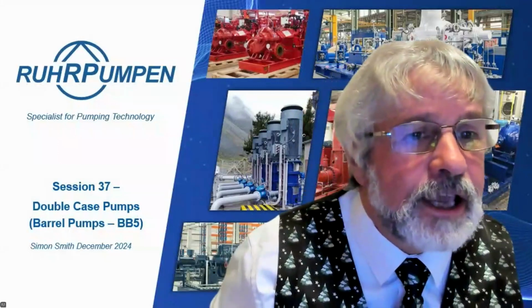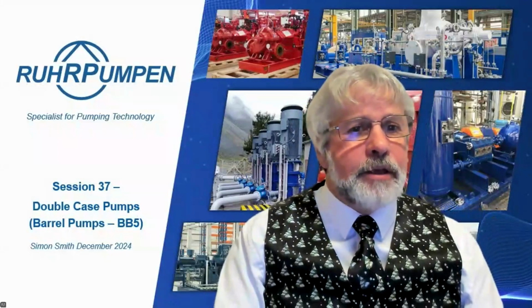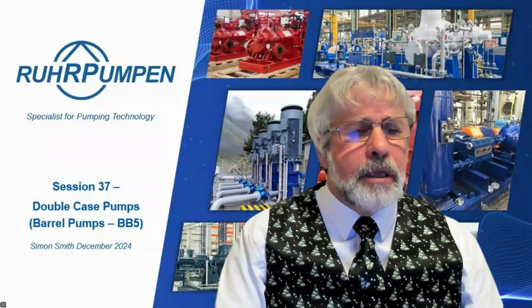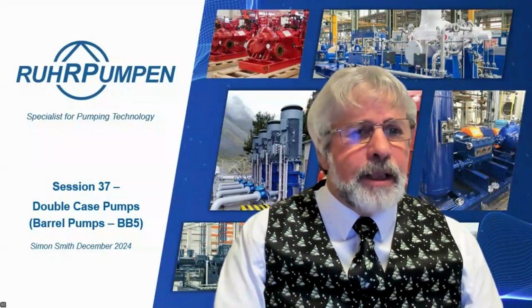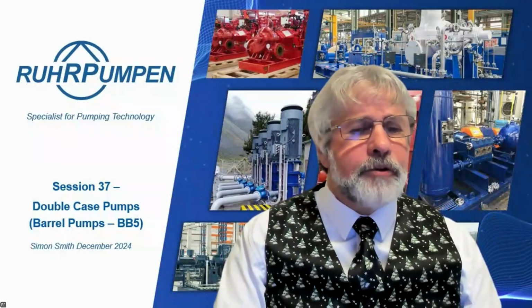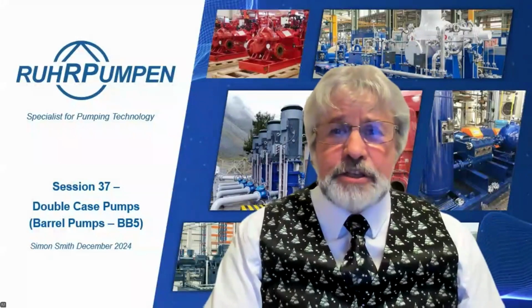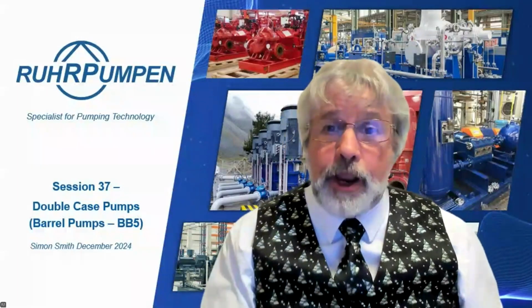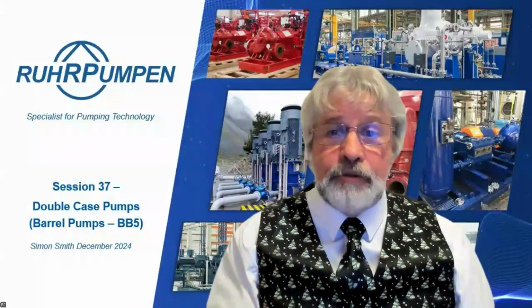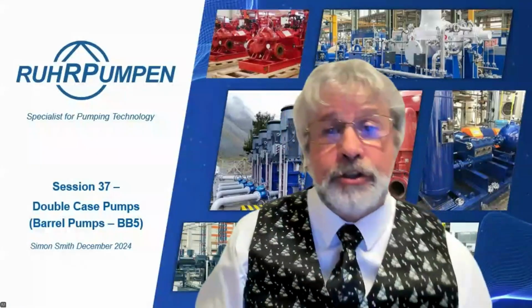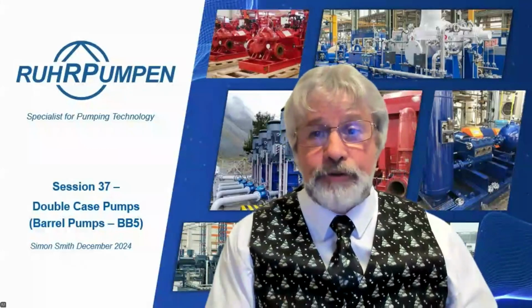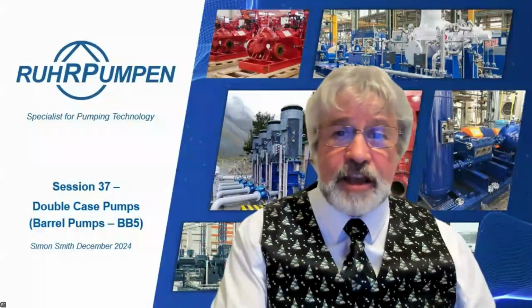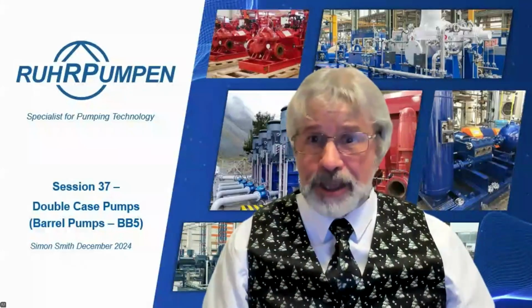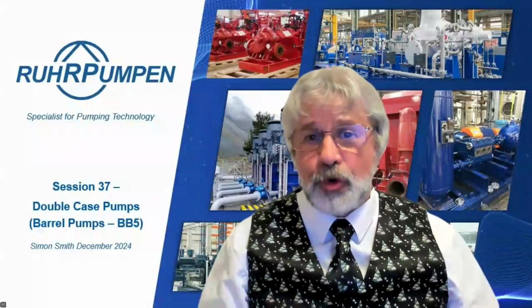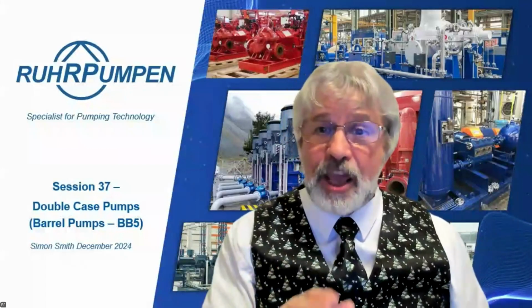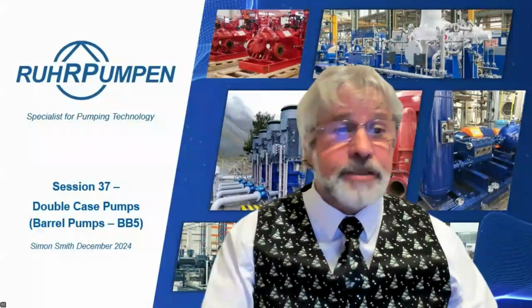Anonymous attendee has said, how can one prepare themselves for hydraulic and mechanical design of BB5s? Not quite sure what you mean here. At the very early stage, if you're a process and mechanical engineer at an EPC or end user, for example, get the pump manufacturers involved at a very early stage. Give them your preliminary duties, process conditions, and they will give you their recommendations at the early design stages, so you know whether you're going to need a double case pump or a single case pump, whether you're going to need forced feed lube systems. All this can be sorted out at a fairly early stage as soon as you get your preliminary process conditions.